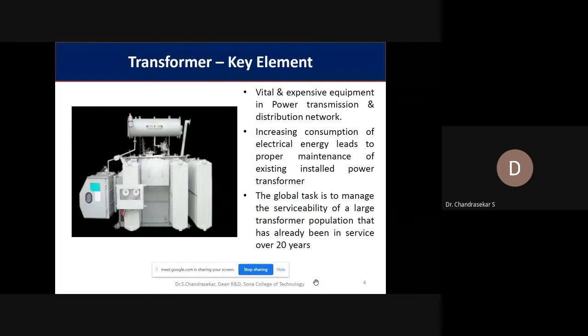As I already told, there are so many transformers on the distribution side that have been in service for more than 20-25 years and are still running, often under overloaded condition. In many places the fault happens because of the overloaded condition, because it is overheated. Naturally, the oil insulation inside the transformer degrades, which results in short circuit, and therefore it bursts, and there are so many issues happening in transformers.